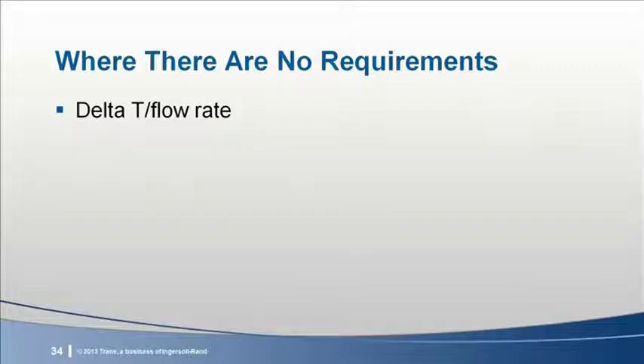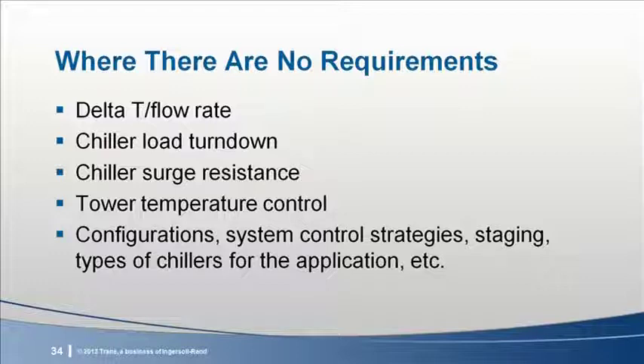Other areas where there are no requirements include chiller turndown and surge resistance. Tower temperature control, as Mick will show us shortly, is very important. Configurations, system controls, staging, and types of chillers to use for various applications are also areas where the designer is permitted to use his or her discretion. But these decisions affect chiller plant performance a great deal and lead to a range of minimally compliant chiller plant performance, as if building type, climate, and other factors didn't give us enough variability. You may be asking, how did the 90.1 committee and the team from the Pacific Northwest National Lab model the stringency improvement from one version of the code to the other? Well, we used standard design practice for system selection and guidance from the performance path baselines in the absence of prescriptive requirements.